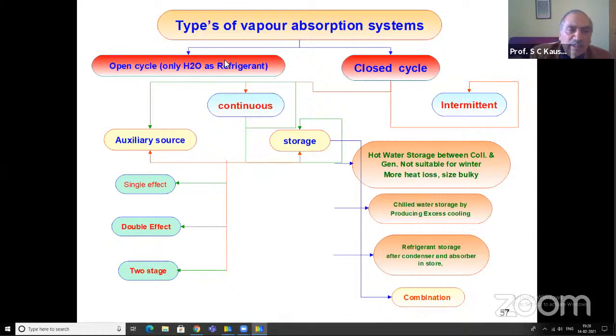Now, the difference between the closed cycle and open cycle. For a closed cycle system, the system is exchanging only heat and work with the surroundings. But for open cycle systems, not only heat and work are exchanged with the surroundings, but even mass exchange of the working fluid with the surroundings takes place. If the working fluid is ammonia or any other working fluid and it is being exchanged with the atmosphere, it is not desirable, it is a health hazard. So necessarily, we have to use water as a refrigerant in open cycle vapor absorption systems.